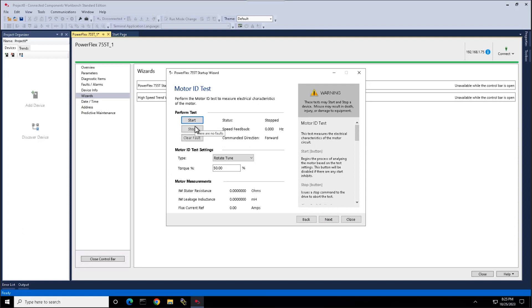Here is the motor ID test. If you have an uncoupled load, you can use a rotate tune. If you have a coupled load, you can do a static tune.